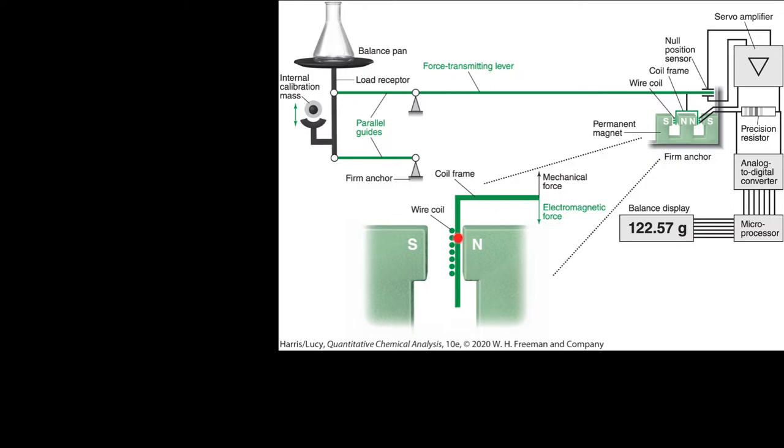What this does is it pulls out a wire from in between the poles of a magnet. So this mechanical force upwards is actually uncompensated right now, and so an electromagnetic force is used to oppose it to bring it back into balance again. And so how does it know to apply this kind of force? Well, there's a null sensor position right here.